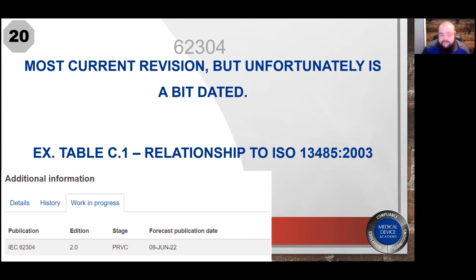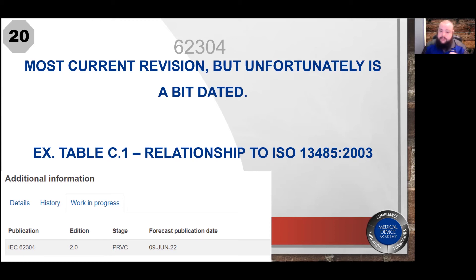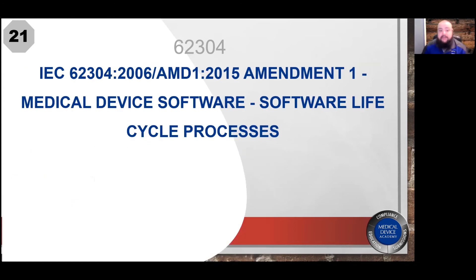The accepted current version of 62304 is the 2006 date revision with the inclusion of the 2015 amendment. Unfortunately it's a little dated — you can see in Table C1 that the relationship to ISO 13485 references the 2003 date revision, whereas 13485 is currently at the 2016 date revision. A second edition of IEC 62304 could be released as soon as June 2022, but for now we have IEC 62304:2006 plus Amendment 1:2015, and the good news is that this has a stability date through 2025.